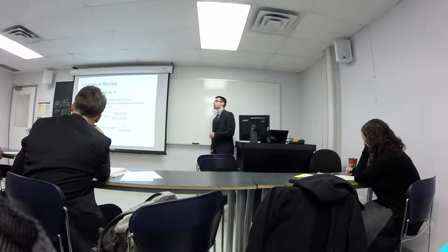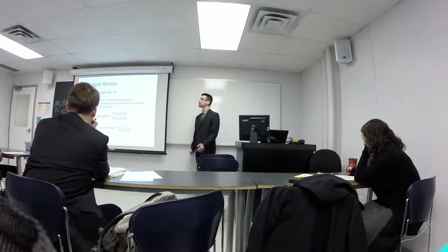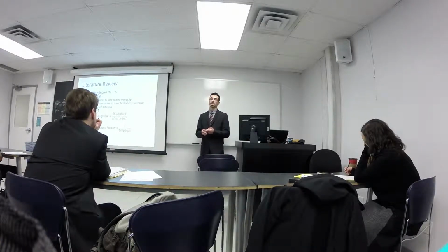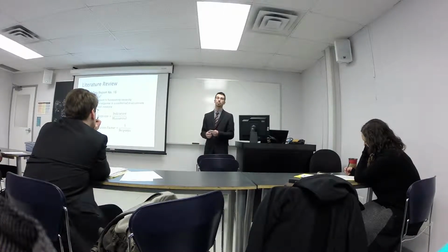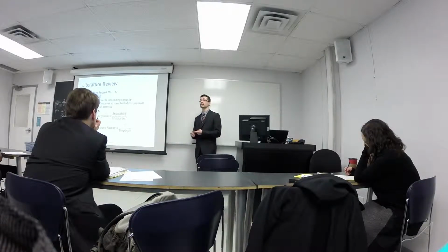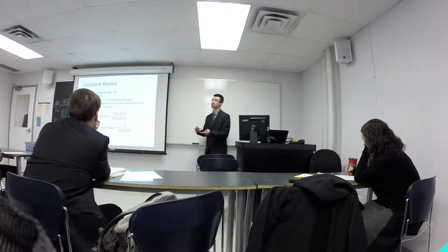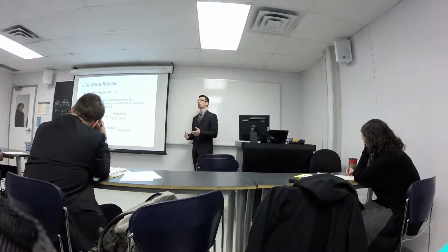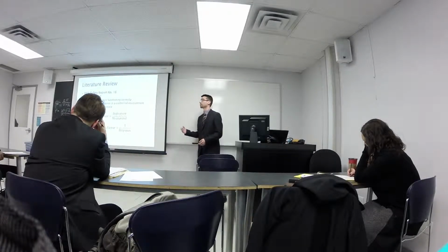As per literature review, I was following an IAEA guideline for calibrating radiation dosimeters. Basically, you want to calibrate because you want to ensure that the instrument is actually functioning as it is intended to be. You want to be able to test it in a controlled environment, test the response of it to different, for example, energies, angles, etc. And finally, you want to optimize the actual accuracy. So by coming up with these calibration factors, we're able to optimize overall the accuracy of the dosimeter.